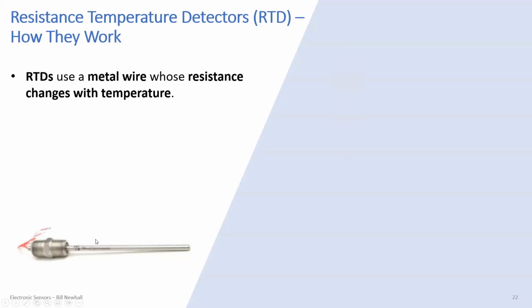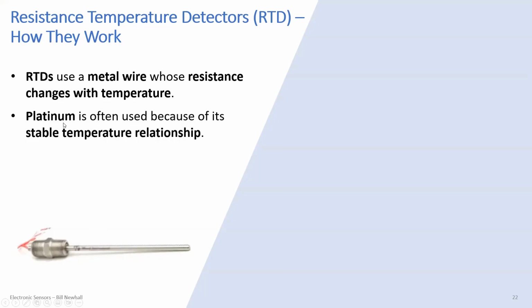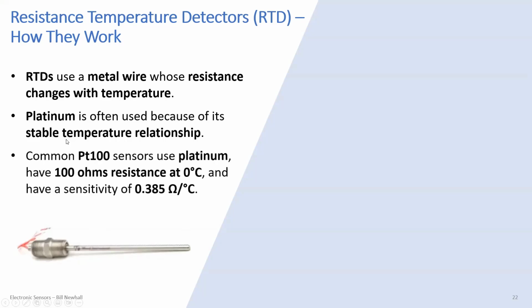So RTDs use a wire, and it's a wire with a known resistance versus temperature characteristic. So you're basically just measuring resistance, you're hoping for a wire that has a good resistance tolerance. The metal that's often used is platinum because it has a stable temperature relationship. And so you'll see RTDs labeled as a type PT100. Those sensors use a platinum wire, and they have 100 ohms resistance at 0 degrees C. And then that resistance changes based on temperature. And so this is the resistance change per degree C, 0.385 ohms per degree C.